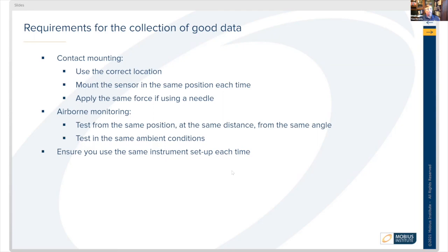For instance, if you're listening to compressed air leaks, you should establish a route that specifies where you're standing, where you're pointing the device, how far off the floor, etc., so that you're collecting consistent data under the same ambient conditions.